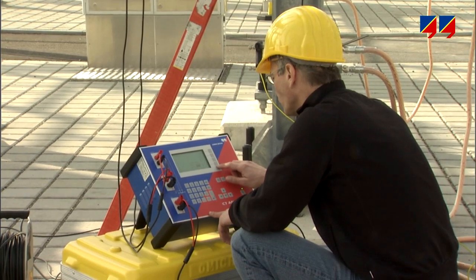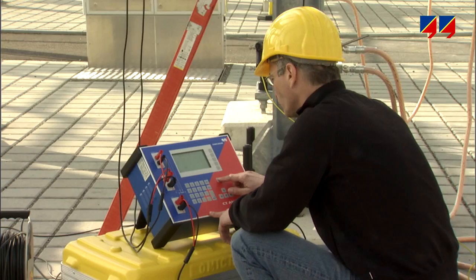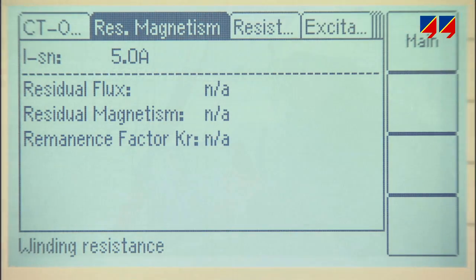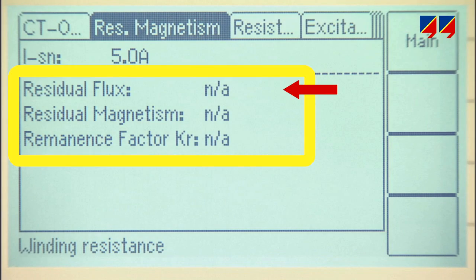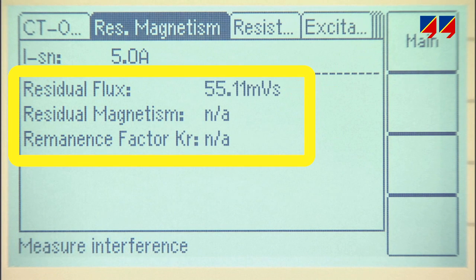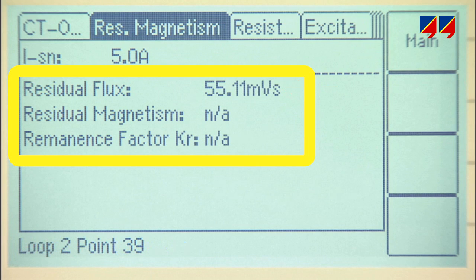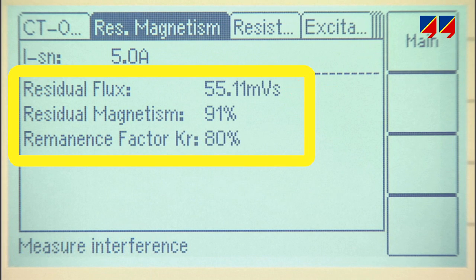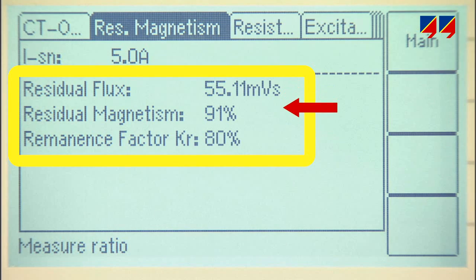With its remalyser function, CT analyzer can determine the extent of magnetic remanence present in a CT core. It determines the value of the magnetic flux in the core and the saturation flux PSIS at the knee point, as defined in IEC 60044. The measured value is then expressed as a ratio to the PSIS.